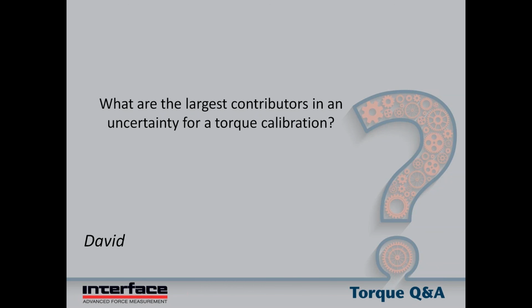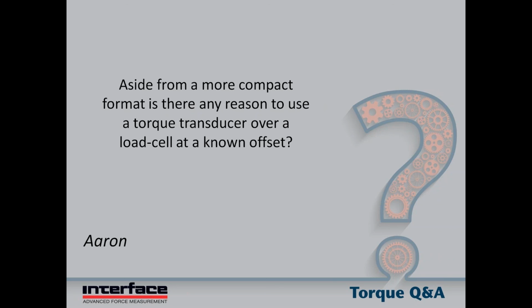Good answer, Chris. Moving on, aside from a more compact format, is there any reason to use a torque transducer over a load cell at a known offset? Yes. In many cases, the load cell is less expensive, so that's a good reason. In some cases, you can get better accuracy, or at least every bit as good of accuracy.